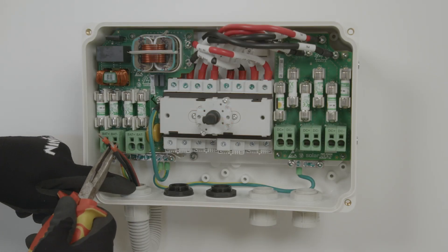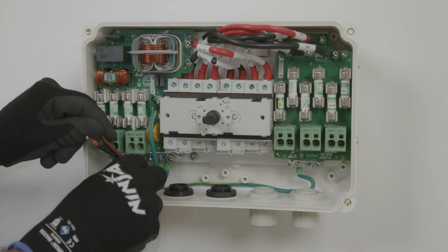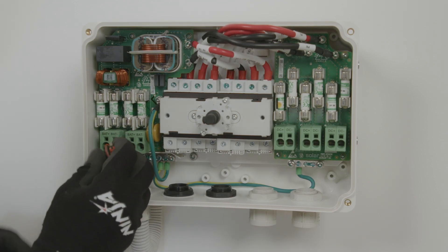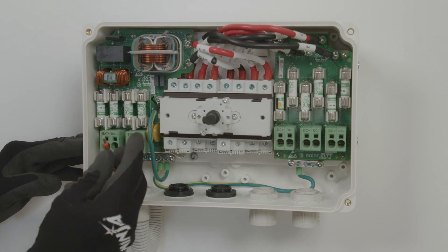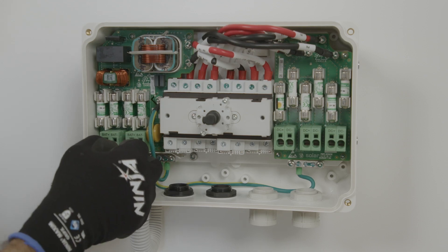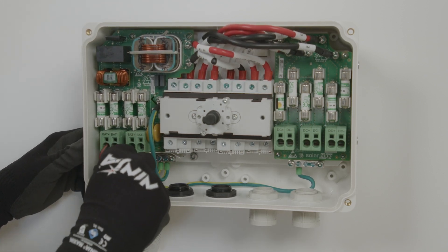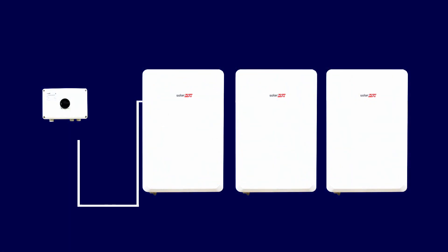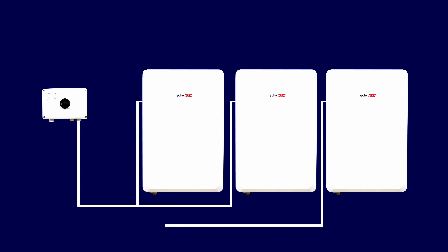We're now going to bring the battery DC into the first terminal block. This DC combiner has the provision to take inputs from three SolarEdge home batteries. Two of them need to connect together via the Y branch connector, and the third directly into the combiner. The combiner is also used for LG Prime batteries.